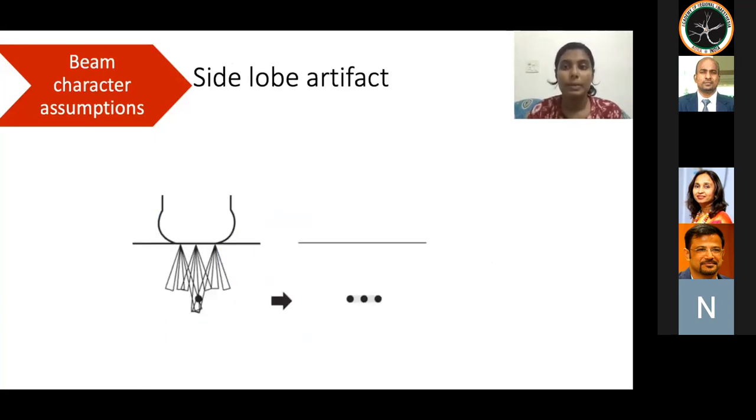This side lobe artifact happens frequently with high frequency linear probes. Side lobes overlapping are much more prominent, more distal to the probe. Unfortunately, this artifact cannot be diminished with simple ultrasound settings. We can try adjusting the focal zone and to have a better lateral resolution.